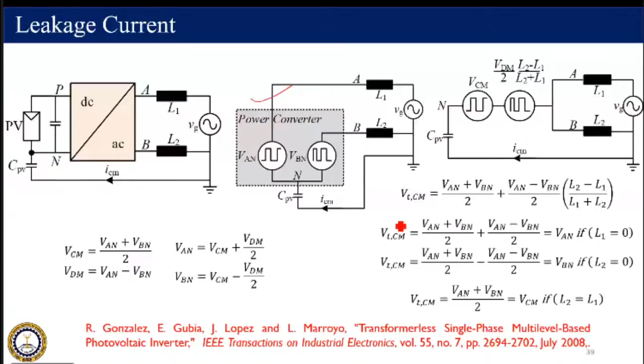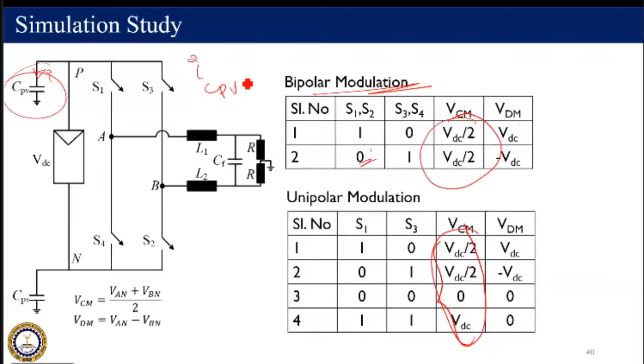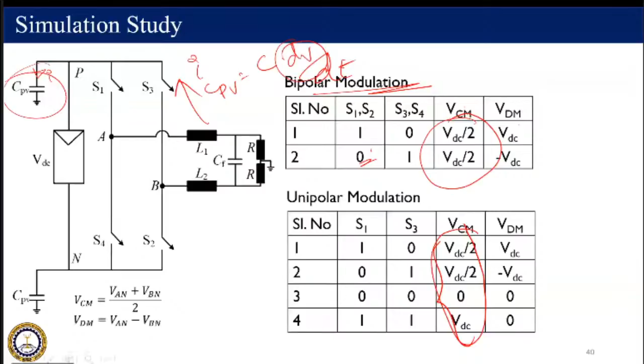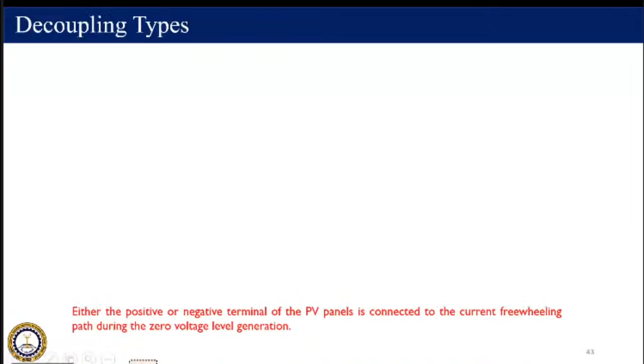When such a varying common mode voltage is generated, it is going to cause a higher leakage current through the parasitic capacitance, because we know the leakage current is nothing but C into dV by dt. Right? So the higher the dV by dt, the more the leakage current. So this dV by dt has to be limited. We have several topologies available for limiting it. One of the popular techniques is to go for a decoupling either on the DC side or on the AC side.